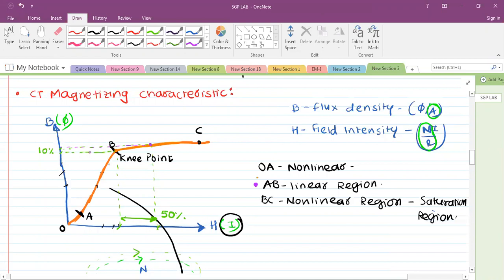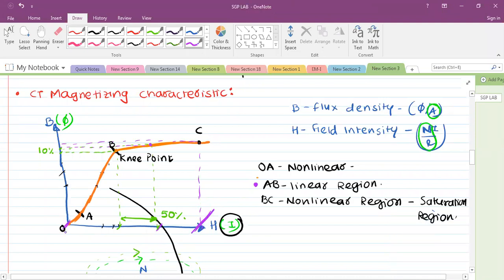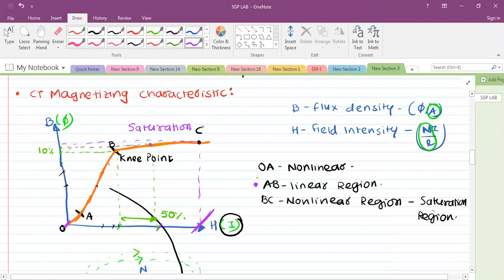But somehow, due to any reason, if the operating flux density of any machine goes beyond this, then the machine will draw large magnetizing current. And if you keep on operating the machine in this range, let's say further, then you can see the magnetizing current requirement is too large, and that is what we call the saturation of the core. Saturation of the core, where the magnetizing current requirement to establish the magnetic field is quite large. We will understand in detail what will happen when the saturation takes place, probably in the next lab. But this is how the saturation or magnetizing characteristic looks.